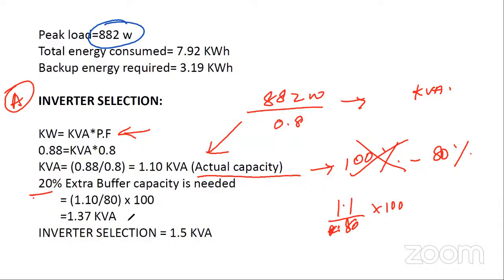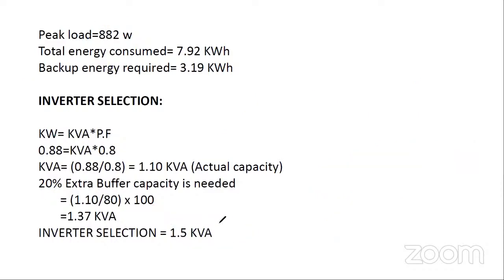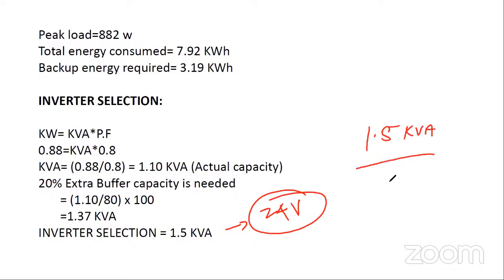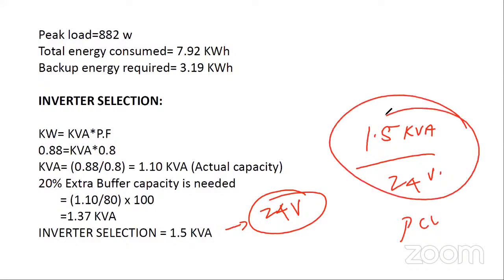If you have a device of exactly 1.37, you can use it, or otherwise go for the next highest rating. Since inverters of more than 1 kilowatt capacity are a 24 volt configuration, our selection is going to be a 1.5 kVA 24 volt PCU. This is our conclusion for the inverter, the one we are choosing for this particular requirement.